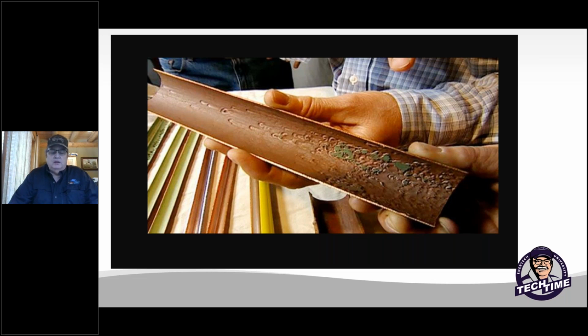Coming from a background where I did a lot of dairy work, we used to see a lot of cows reduce their milk production, and farmers saw them very uncomfortable at the milking parlors. A lot of it stemmed from what we call grounding issues and stray voltage running through the concrete and coming into the animals. This is where a lot of the corrosion came into play, especially in dairy barns, in electrical panels and improper grounding. So this can happen in our industry as well, which I have seen in the last couple of months. People had to replace all the copper water pipes in the geothermal heat pump.